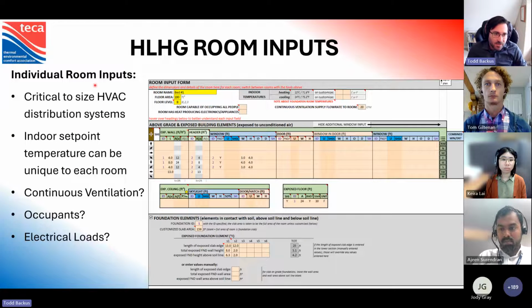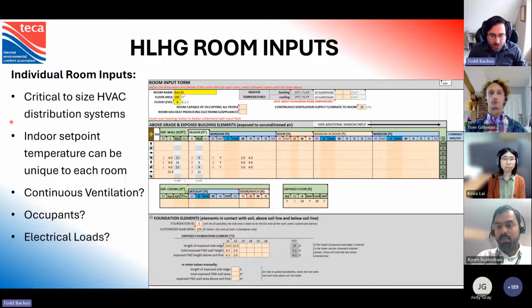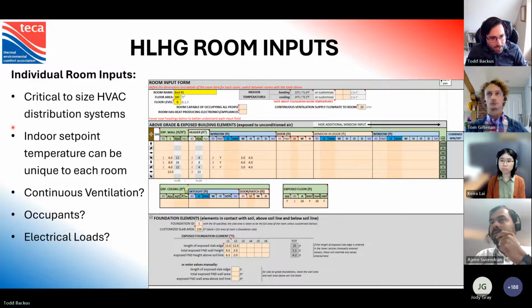Now, the calculator does room by room analysis. This is critical to sizing an HVAC distribution system. Personally, I would never accept a system that was designed off the block load. The block load is fine for high level. So if you're quoting a job, or talking about the overall performance of the building, that is fine. But when it comes to actually sizing your ducts or your radiant loops, you really have got to know what each room uses. You can modify in our software the temperature in each room.